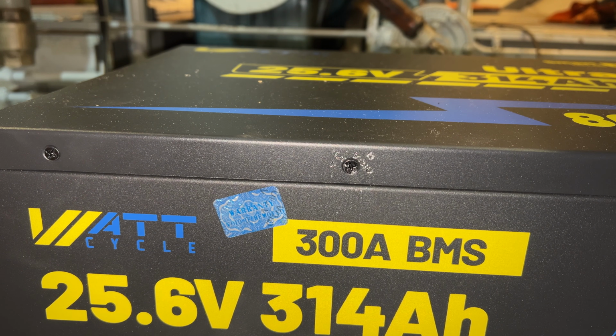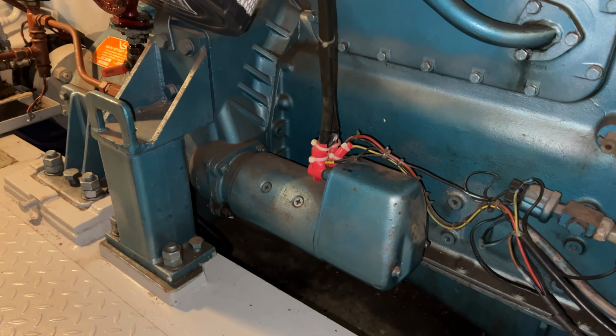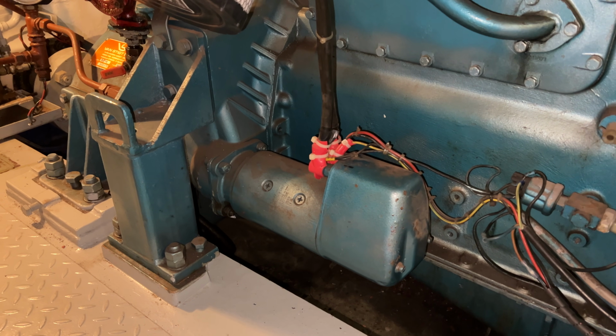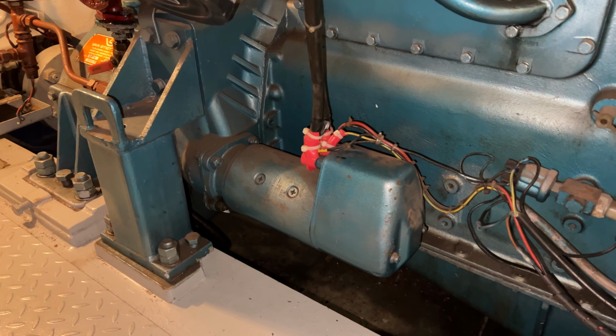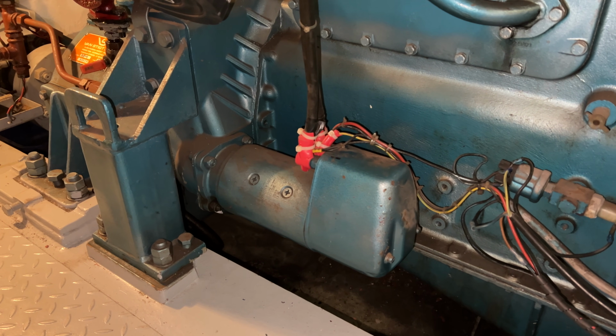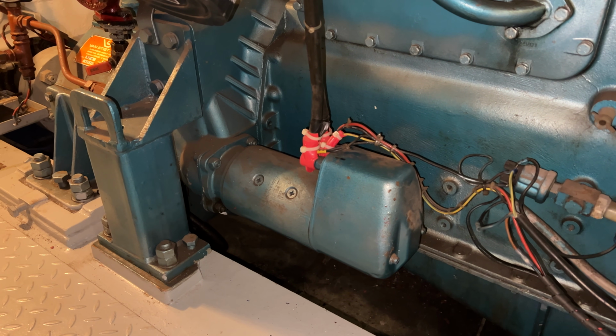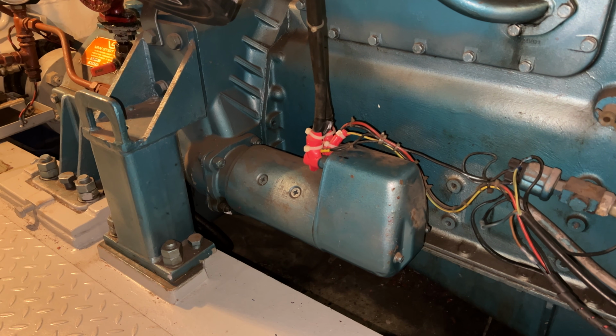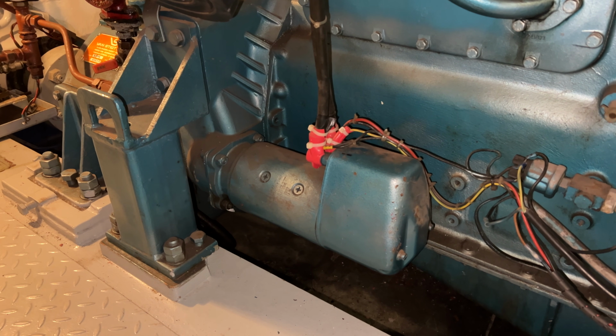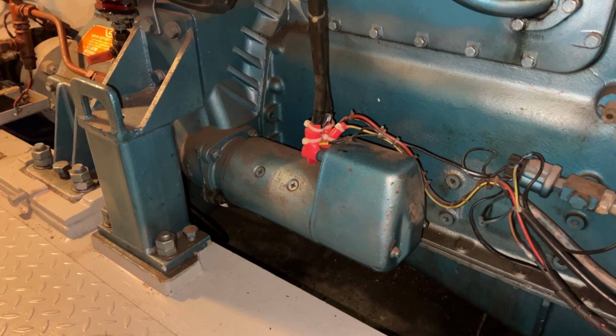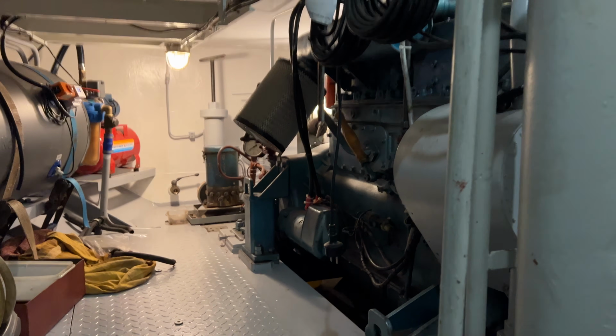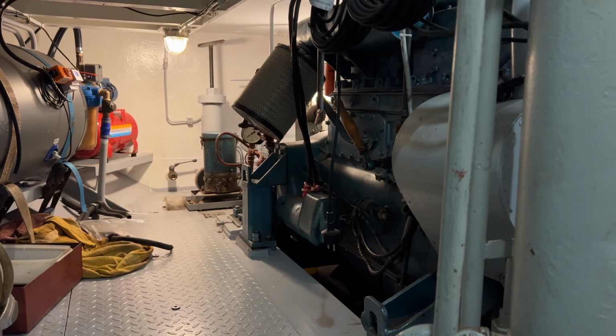The battery has a continuous output of 300 amps, and our starter motor is 5.5 kilowatts, which translates to 230 amps. However, to get the motor up to speed, for the first couple of milliseconds the current can be 2 to 3 times as high. And the short burst inrush current of the battery isn't stated anywhere. So let's see what happens.